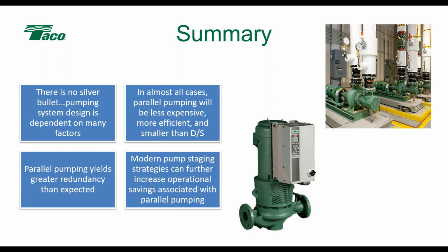Yeah, what you've got to remember is that as you increase speed, the head goes up exponentially. What usually happens is you move far enough right on the curve that your head's gone up faster than the speed and the flow are going up, because you're running over speed and trying to move more water. So you end up running out of pump much quicker, and once you get beyond that maximum allowable, you start to get into an unstable area of the curve. Bad things start to happen because you're changing the thrust on the impeller, both the radial and the axial thrust inside that casing. And that's the one thing that is different with pumps and fans. Fans behave a little bit differently when you go to overspeed. You don't get the same bearing loading.